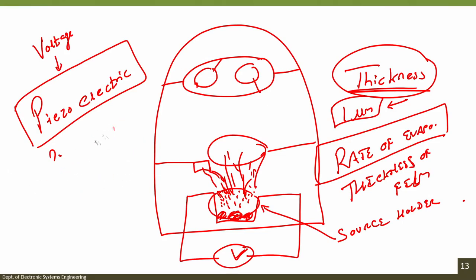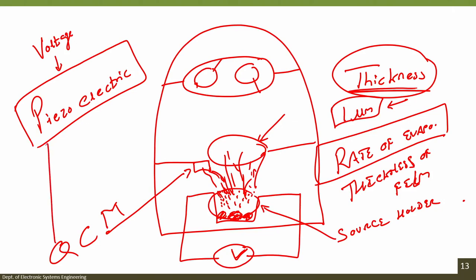The quartz crystal monitor inside the vacuum chamber measures the rate of deposition. The parameter — change in voltage versus deposition rate — is pre-fed into the electronics. Once the desired deposition rate is known (typically given in angstroms per second), you can open the shield and let material deposit onto the substrate.